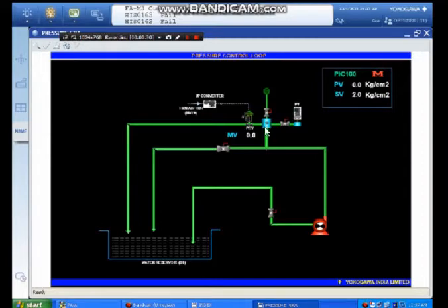The water going out from the pressure head is controlled by a control valve. This control valve is connected with the I2P converter. It will be getting a data signal from the DCS. This pressure gauge is also a normal Bourdon gauge which will be showing the readings. There is also a DPT connected which will be sending the pressure inside this pressure header to the DCS.